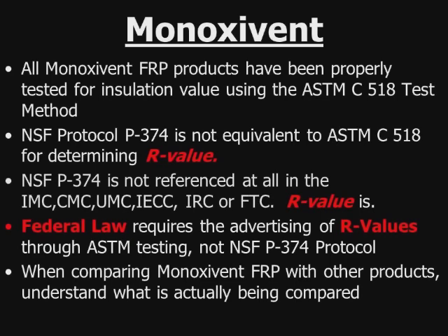Okay, now going back to our products, again, we offer single and double wall insulated products, and all of our products have been properly tested to the C-518 test method for R value. And to reiterate our statements, the P374 protocol is not equivalent to the test that we use to test our products. It's not at all referenced in any of the codes that you saw today, whereas R value is.